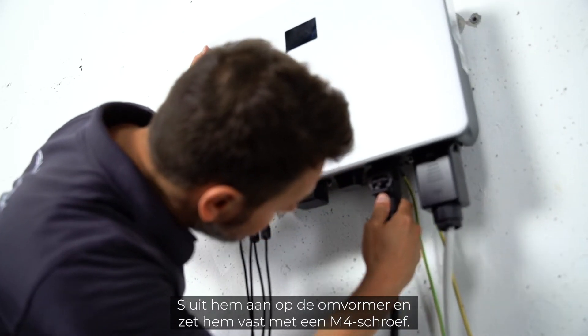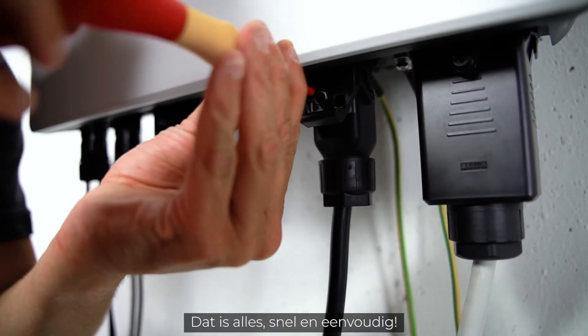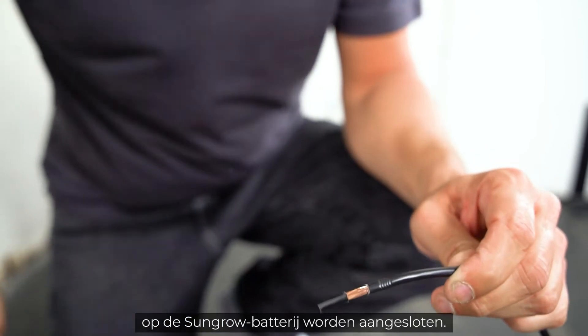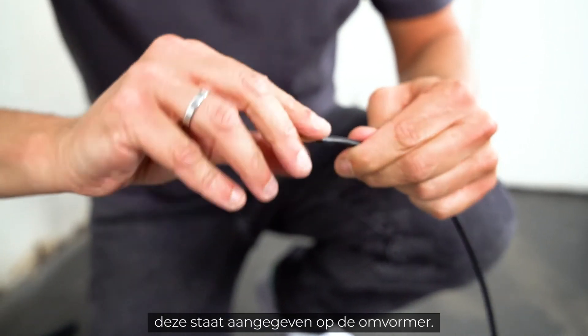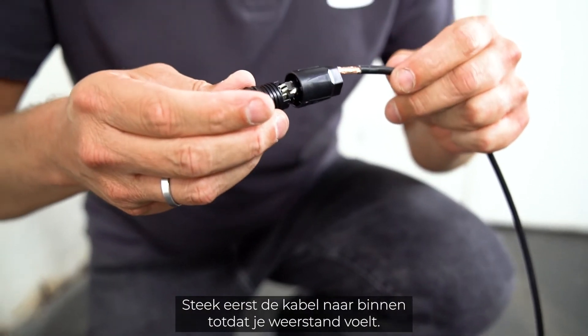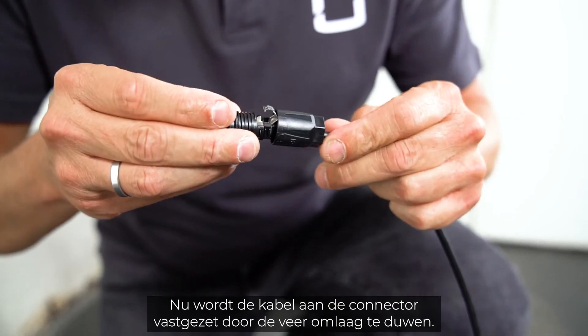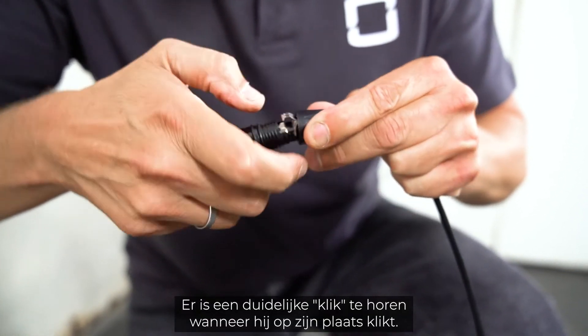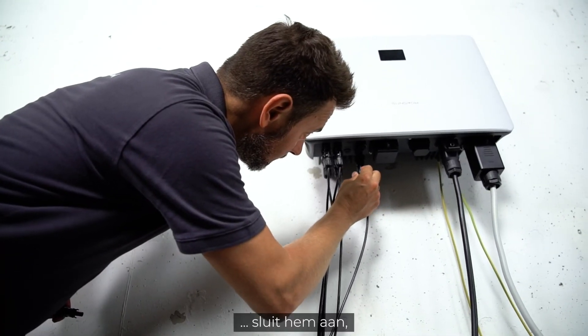Connect to the inverter and fix it with an M4 screw — quick and easy. To connect the single-phase hybrid to the Sungrow battery, you have to use SUNCLIX connectors. Pay attention to the correct polarity, which is marked on the inverter. First insert the cable until resistance is felt. Now the cable is fixed to the connector by pushing down the spring. A clear click can be heard when it clicks into place. Tighten the plug and plug it in.